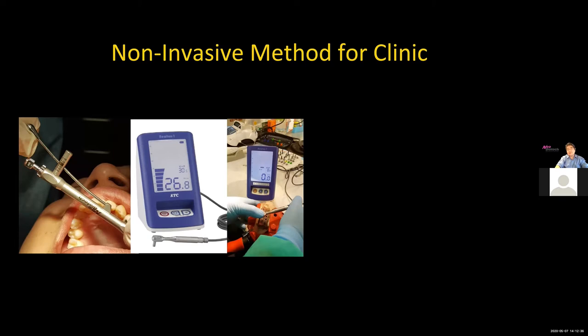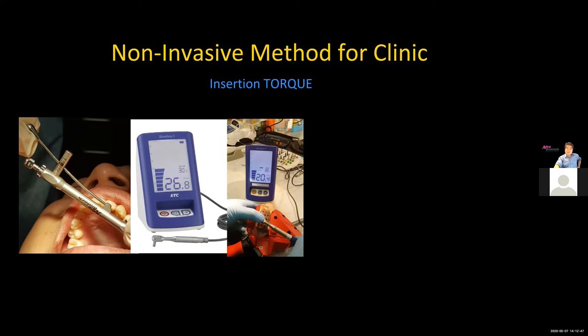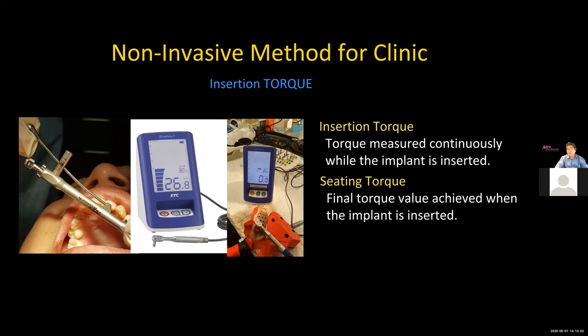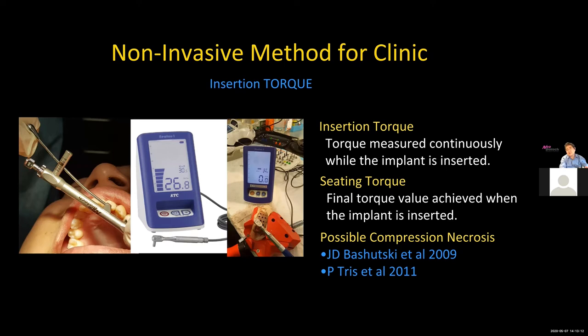The first non-invasive clinical method is insertion torque. Using a digital insertion torque measuring device, it measures the highest torque during implant insertion — the insertion torque, seating torque, or final torque. Though terminology varies slightly, we are measuring the peak torque number during implant insertion.